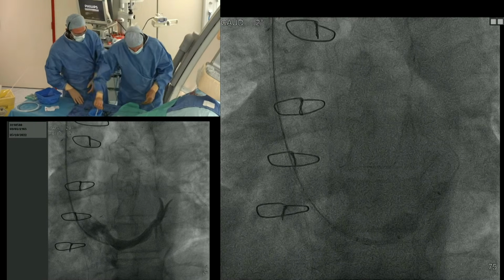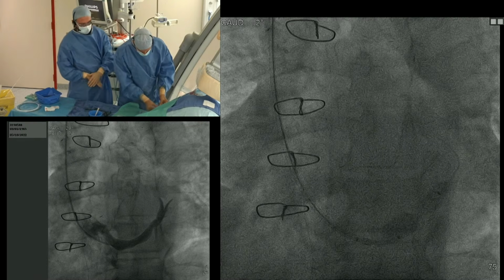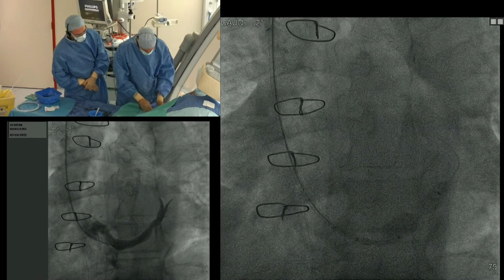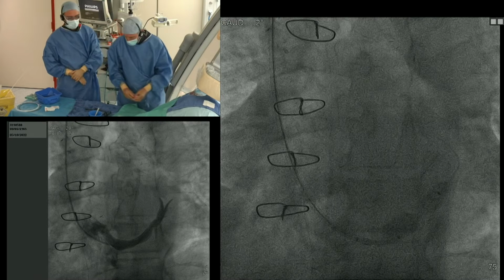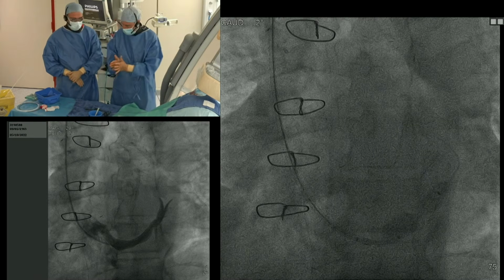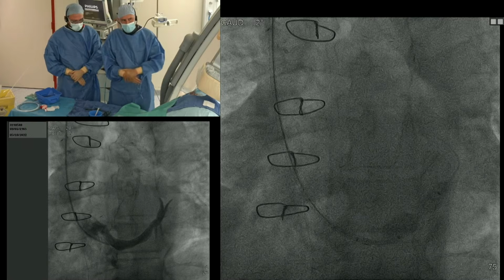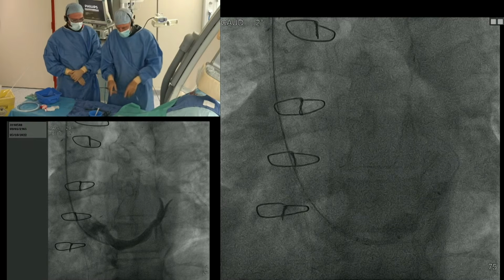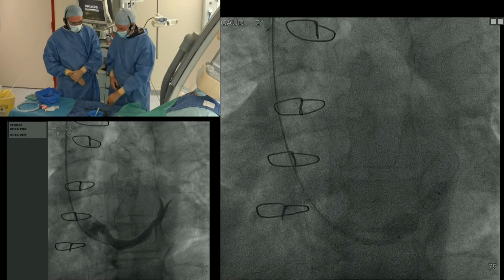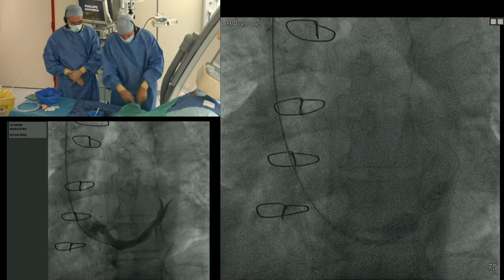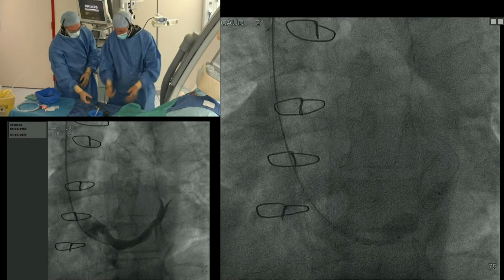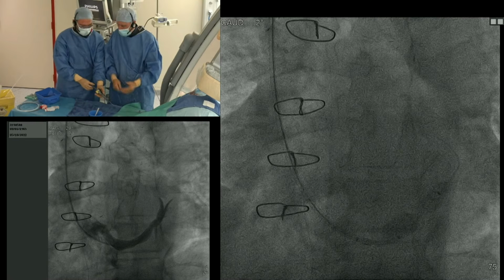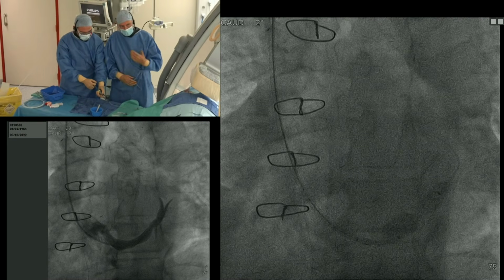That's a very good point, Pierre, because the profile of the balloon is not ideal, and we might have some interaction between the balloon and the device. So the rule is to empty completely the inflator, meaning you deflate everything, and when it's fully empty, we will put it many times at negative pressure to be sure that the profile of the balloon is really ideal.